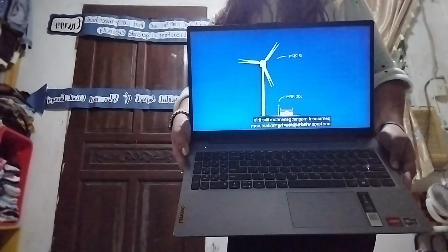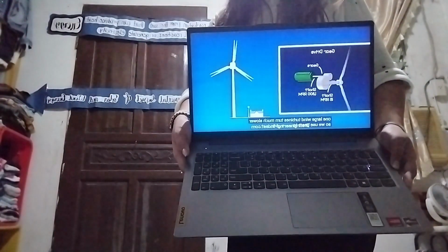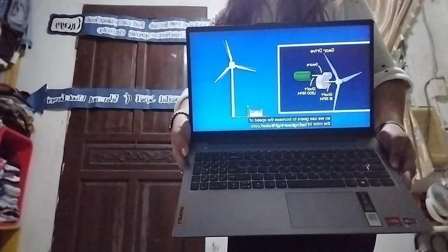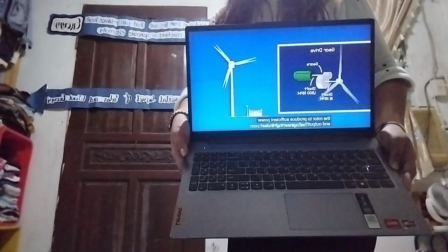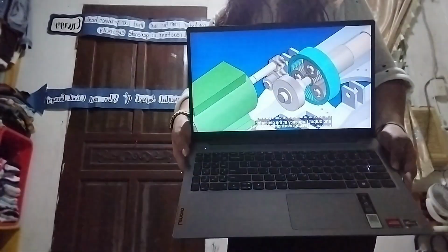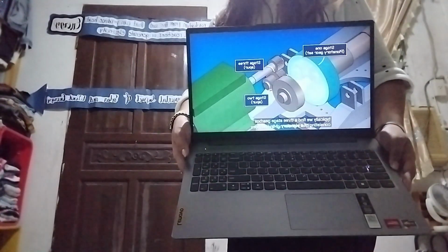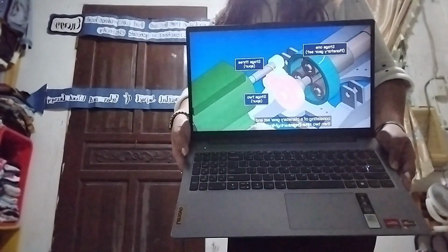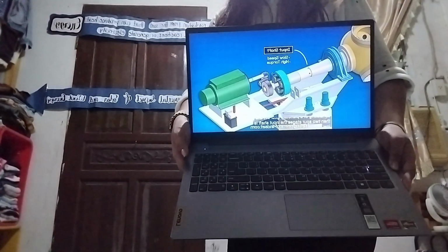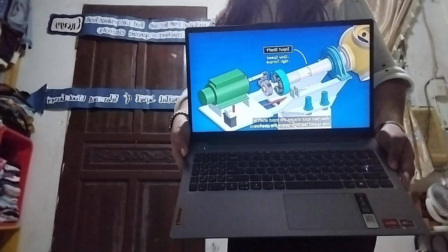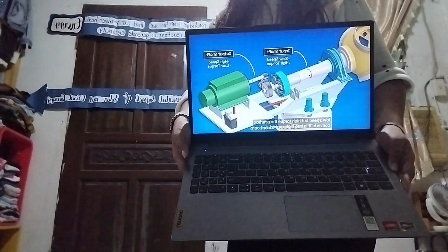Large wind turbines turn much slower, so we use gears to increase the speed of the rotor to produce sufficient power and output frequency at the generator. Typically, we find a 3-stage gearbox consisting of a planetary gear set and then 2 spur stages. The input shaft is low speed but high torque. The gearbox converts this into high speed, low torque.